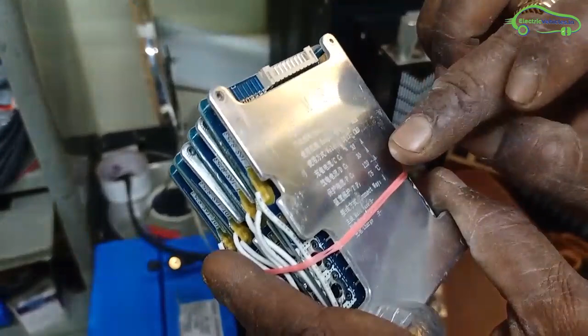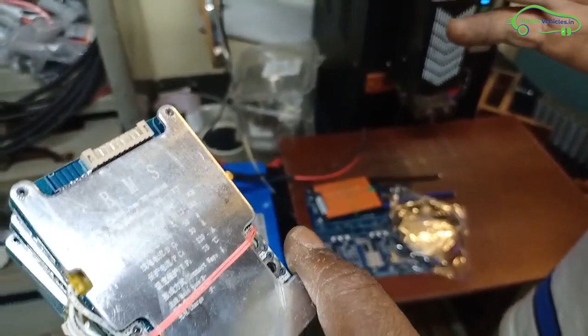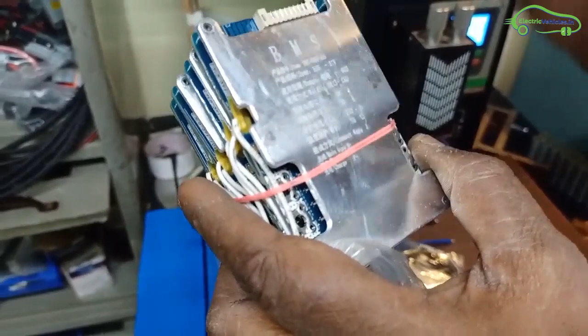So it is not correct. First you check the peak discharge and continuous discharge of the controller, that is the most important. It is not like that if you are making a 100 Ah battery for a 48 volt 20 amp vehicle, you must use a 100 amp BMS. Always check the motor capacity, controller drawing amps, peak amp, and continuous discharge amps of the controller. Then you choose the BMS.